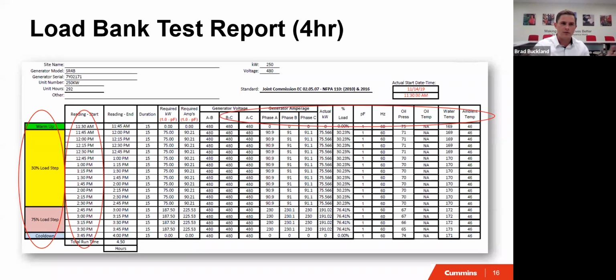And what we're checking here, and how this leads to seeing things you wouldn't see in a visual check, or changing filters or looking at your control panel, is these phases right here. And then it says load percentage. You'll be able to see if there's any variance in the change, or if there's any problems that might be in the alternator, which is the spinning that's actually creating the power. And you'd be able to detect high pressures, low pressures, temperature changes within the unit while it's testing on a cycled load. So you'd be able to detect a lot of things that you wouldn't necessarily be able to see before.